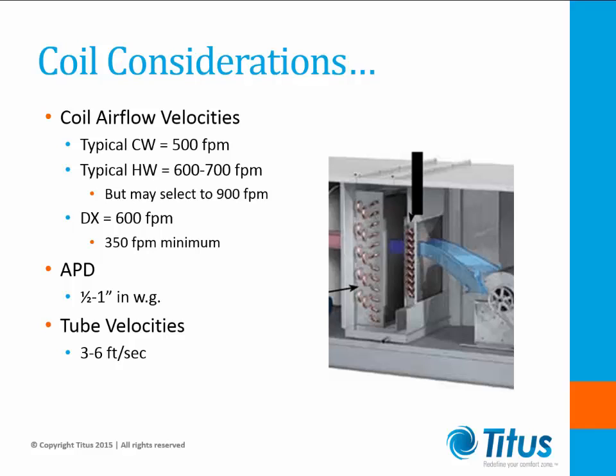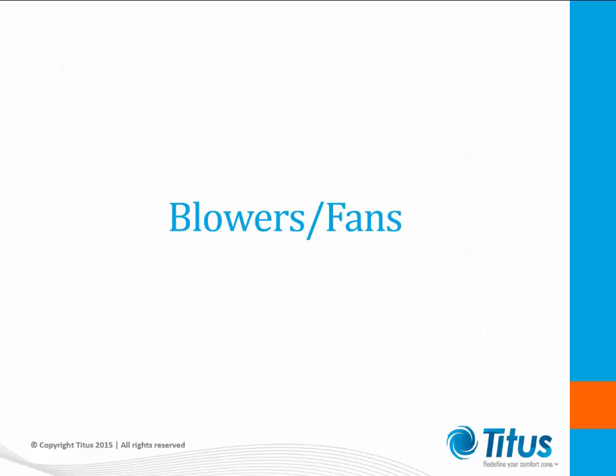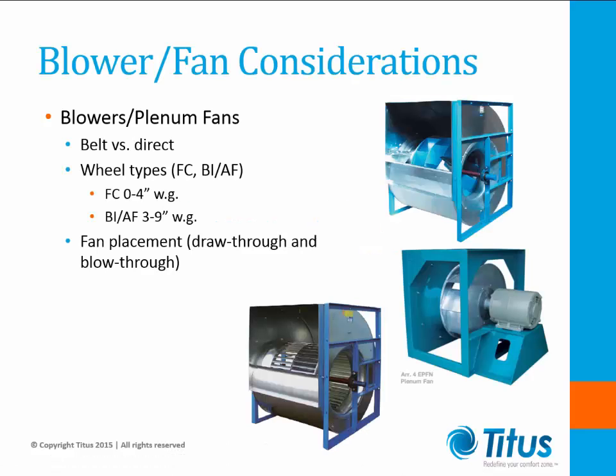DX coils tend to run a little higher than cooling coils, but do have concerns if the airflow velocity is below 350 feet per minute. If space allows, making coil selections larger to reduce velocity, such as 300 to 400 feet per minute readings, allows a small percentage first cost, but saves big in supply fan horsepower over the life of the unit. Tube velocities typically are found between 3 and 6 feet per second, and this reduces the chances of laminar flow within the coil. Now let's take a look at the blowers and fans within the units.